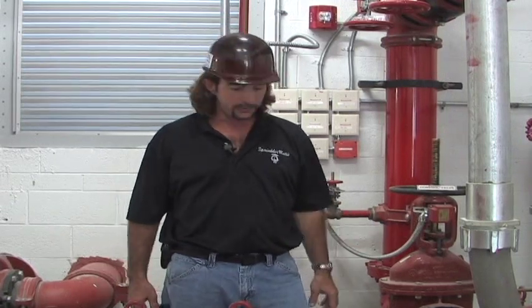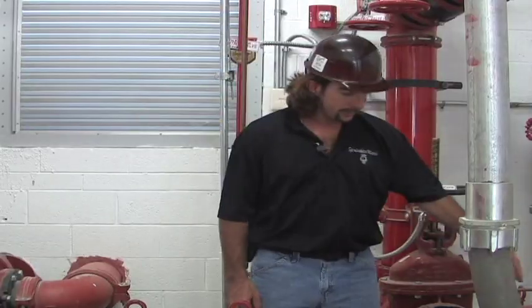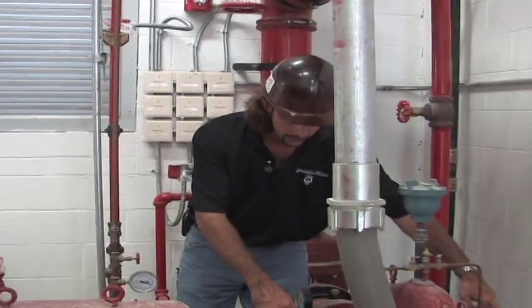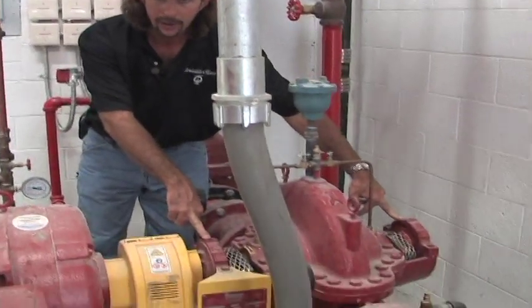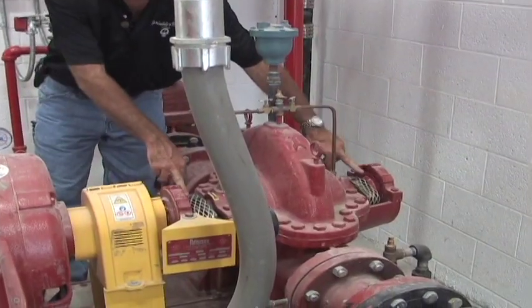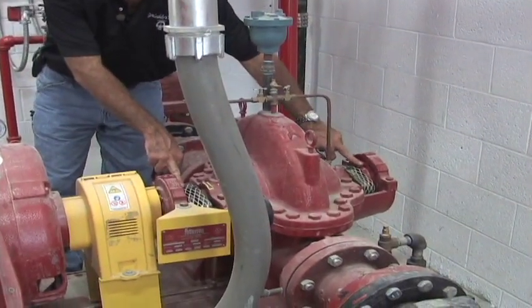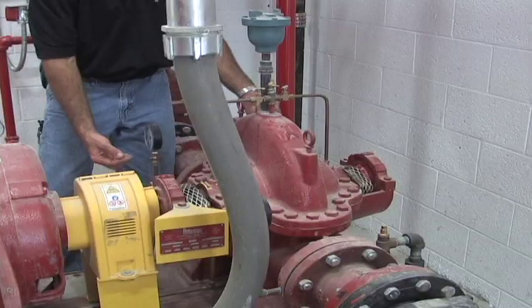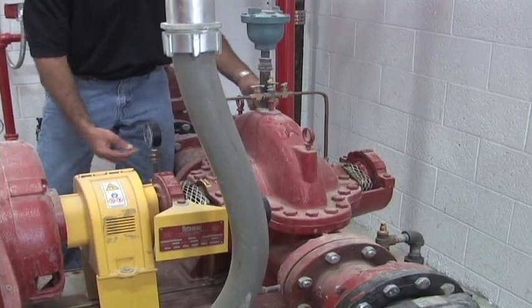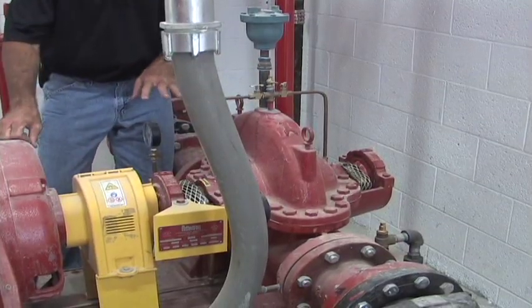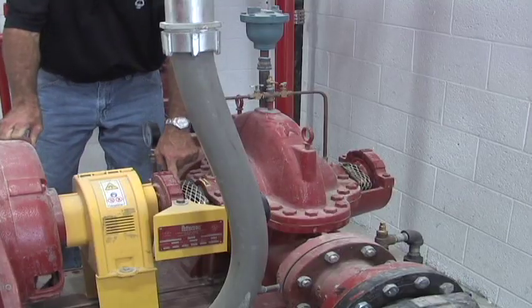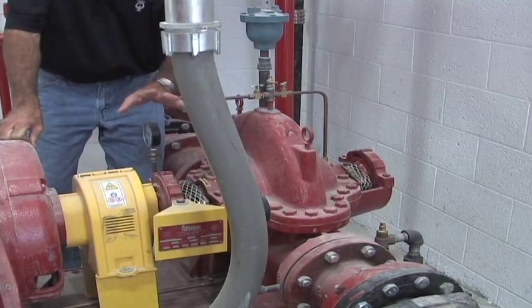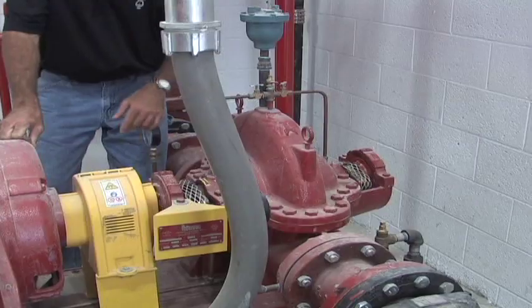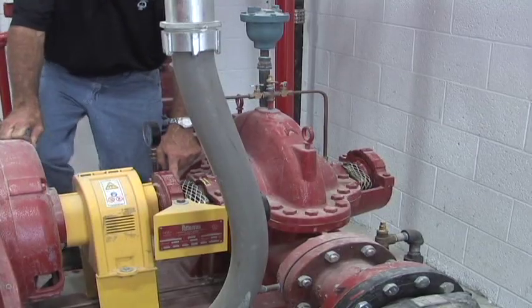We really don't have anything, no fluids naturally that we have to check. What we do is we have our outboard and we have our inboard bearing housings. Both at the top have a grease fitting, and at the bottom they have a little Allen wrench or a set screw that comes out. On an annual basis, we're going to take grease, maintenance or whoever does it, your fire sprinkler contractor. The only maintenance skid is this grease fit.